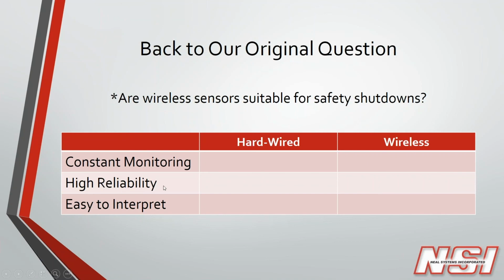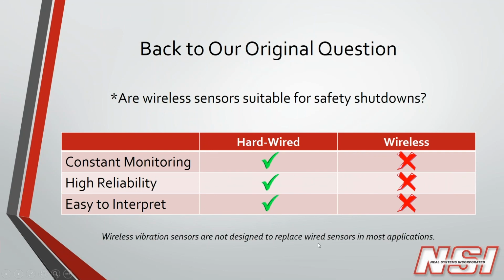And then the last thing is you can't have false alarms telling your maintenance team that you want to create a mentality that when the alarm goes off, you don't necessarily stop what you're doing. The alarms need to be easy to interpret and they need to be clear exactly as to what's going on when the alarm goes off. What is our response to the facility? So in all these cases, we as Neal Systems recommend that you always go with hardwired. It's going to be a safety, and you need to really keep the hardwired purposes separate from the purposes that you're trying to accomplish with your wireless sensors.